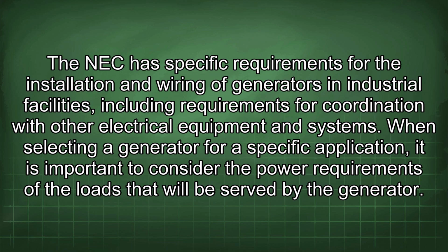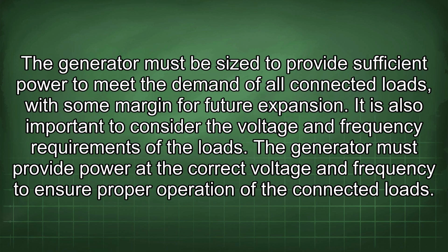When selecting a generator for a specific application, it is important to consider the power requirements of the loads that will be served by the generator. The generator must be sized to provide sufficient power to meet the demand of all connected loads, with some margin for future expansion. It is also important to consider the voltage and frequency requirements of the loads. The generator must provide power at the correct voltage and frequency to ensure proper operation of the connected loads.